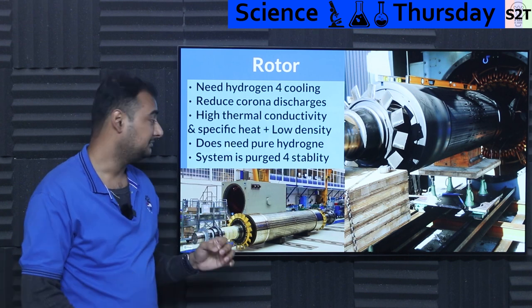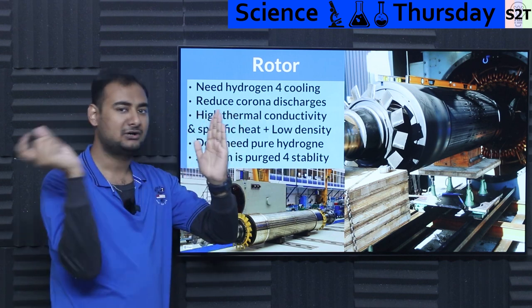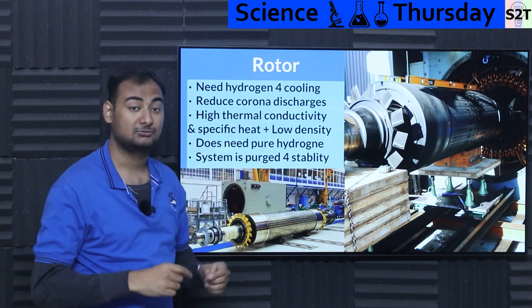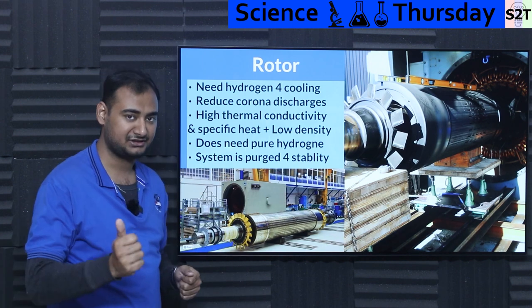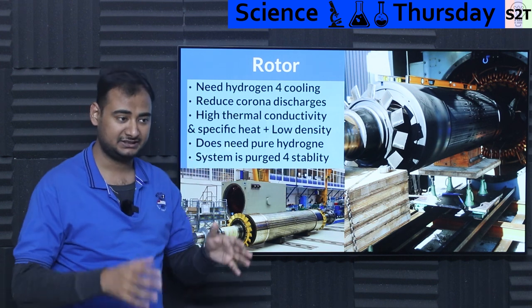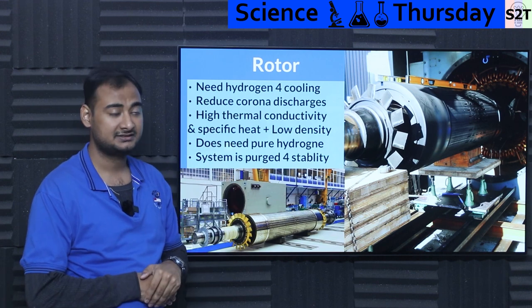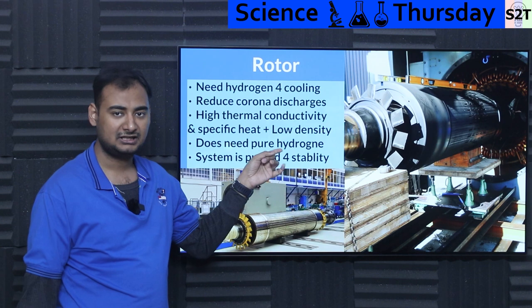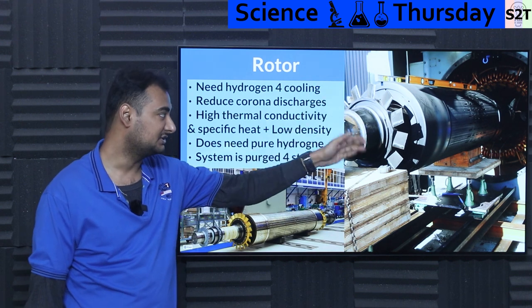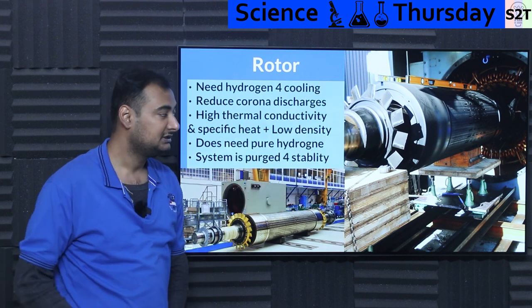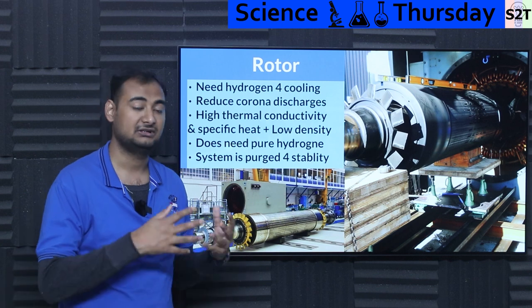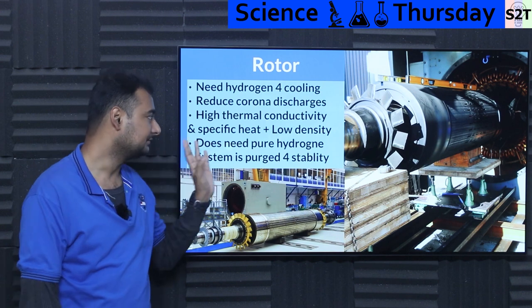Second, hydrogen is a very light element with very high thermal conductivity — it bounces heat from hot to cold components very quickly. A heavier gas like nitrogen won't do that as efficiently. Hydrogen is also good in terms of specific heat — how many joules it absorbs before 1 kg gains 1 degree Celsius — genuinely good. Finally, its low density matters because at 3600 RPM, drag is a big issue. Even heavily pressurized hydrogen has far lower drag than CO₂ or nitrogen because H₂ molecules are tiny. That's why we use hydrogen.